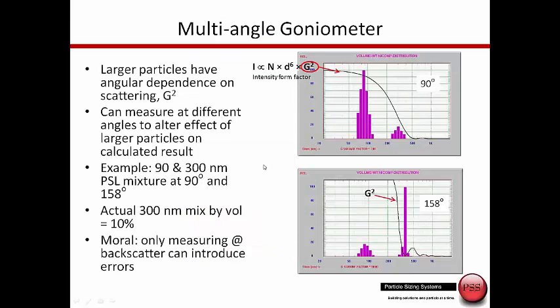This system can be configured to be a multi-angle goniometer. The reason we would do this is typically when measuring larger particles. If they are very small particles, under say 20 nanometers, the scattering is isotropic and the same at all angles. But for larger samples, like a lipid emulsion at 300 or 400 nanometers, we have not only the scattering dependence, which is d to the sixth or diameter to the sixth power, but we need to take in this intensity form factor g squared.